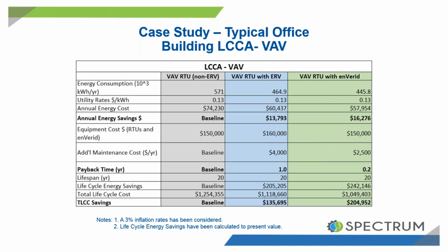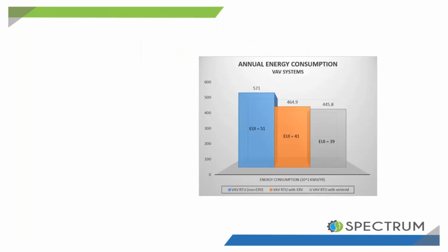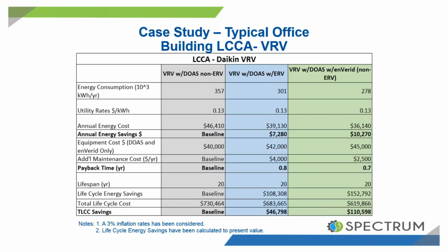Marginal maintenance costs from cartridge changeouts and other service with enVerid versus ERVs, where those wheels might seize or big problems come up or they get turned off. And massive energy savings as well, 16,000 versus 13,000 with an ERV. What this enables you to achieve is a better EUI score, which is very important frequently, especially on new builds. So 51 on your conventional design, all the way down to 39 with enVerid.